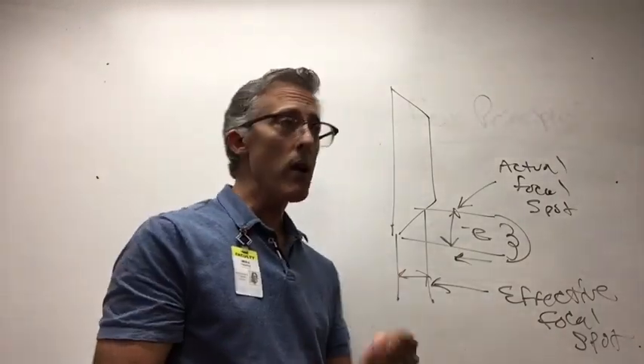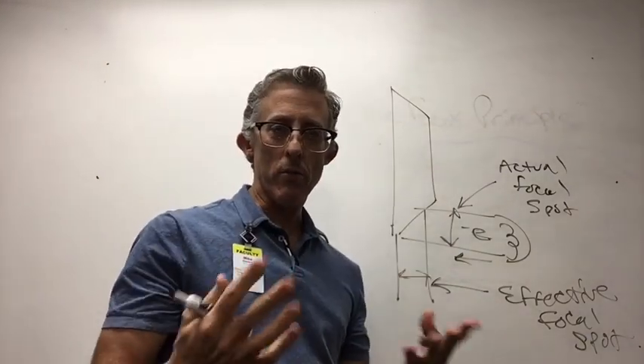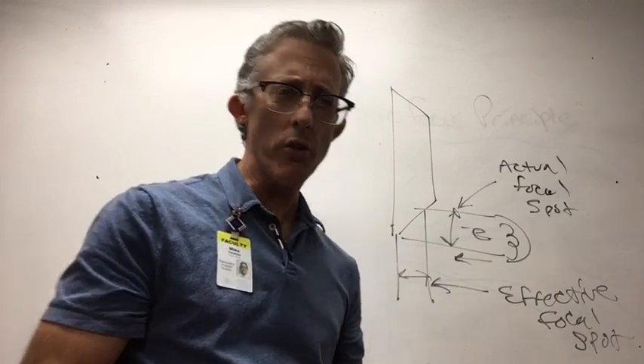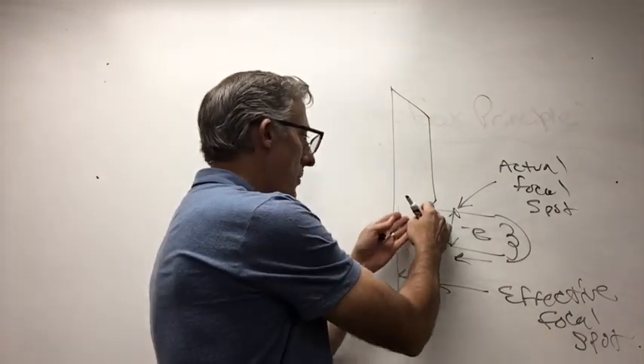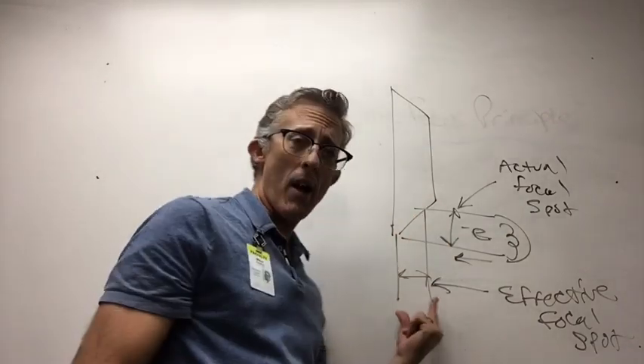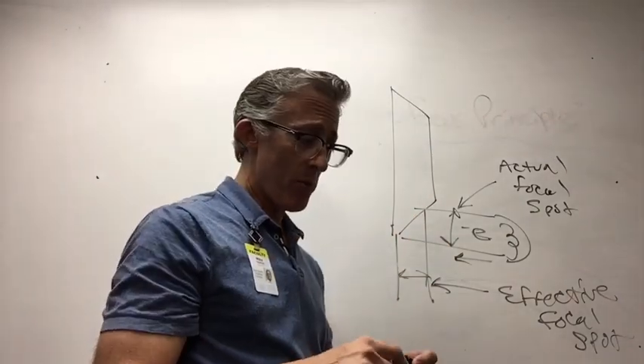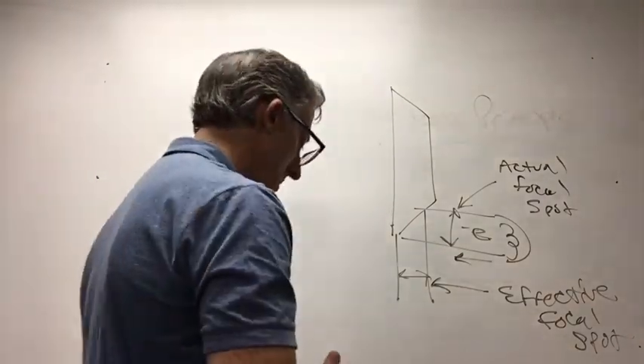So in order to do that, we want to spread those electrons out as much as possible. So we run into a conundrum, don't you think? In spreading those electrons out as much as possible, we then have a wider effective focal spot. How do we get around this? Simple geometry. The line focus principle. It's an amazing thing.